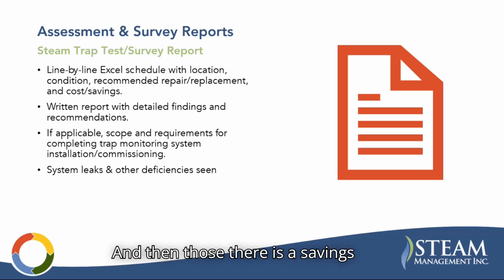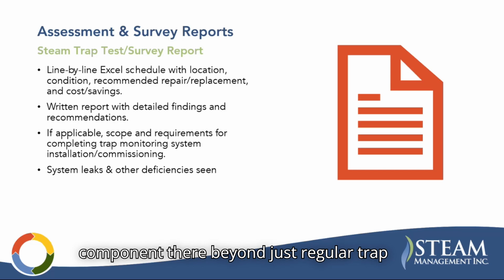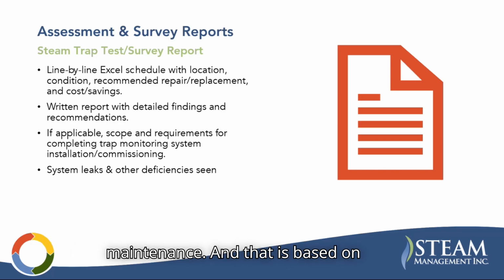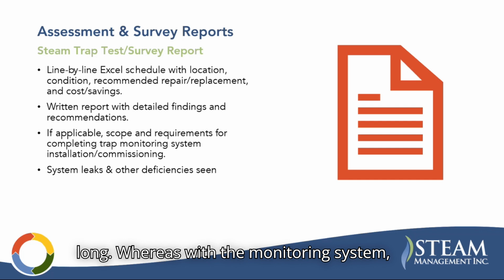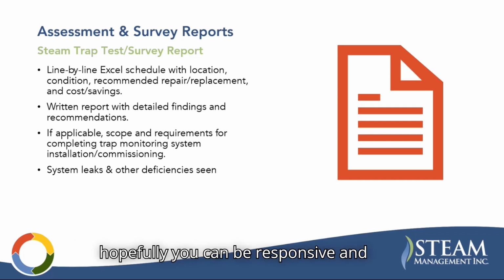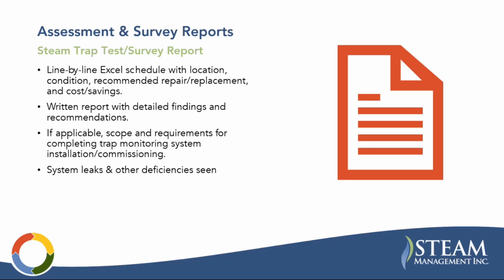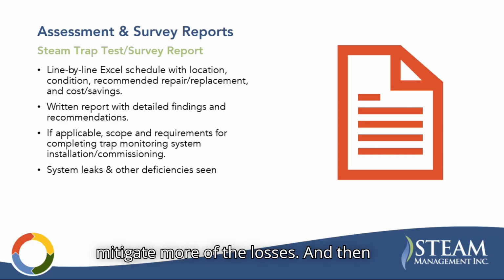And then there is a savings component beyond just regular trap maintenance, and that is based on being able to respond to those leaks more quickly, right? Even if you do a yearly test and repair program, a trap could fail right after your previous test and be failed all year long. Whereas with a monitoring system, hopefully you can be responsive and address those leaks right away and mitigate more of the losses.